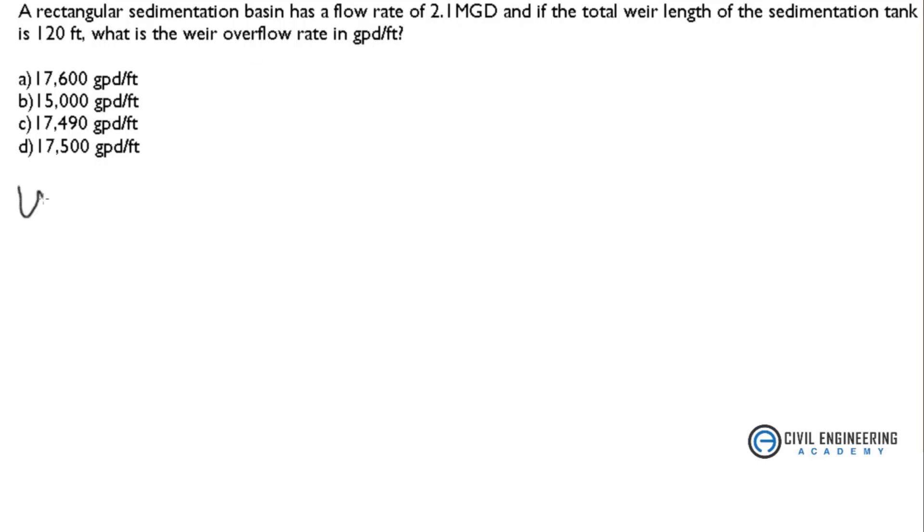We know the formula: weir overflow rate WOR equals flow rate Q divided by length L, the total weir length. It's a direct problem. So we have all values here. We know the flow rate is 2.1 million gallons per day, and our length is 120 feet.